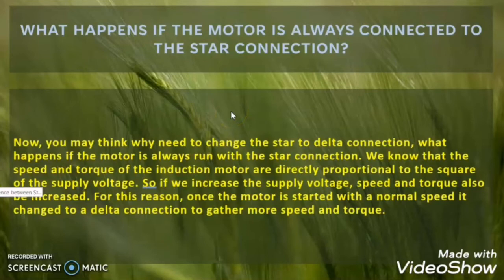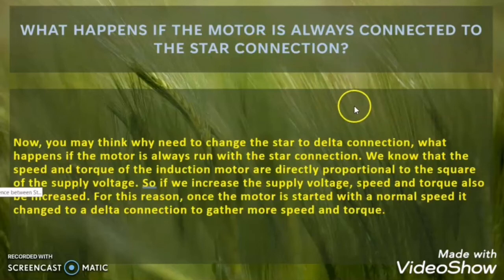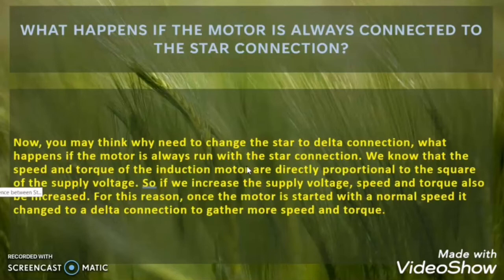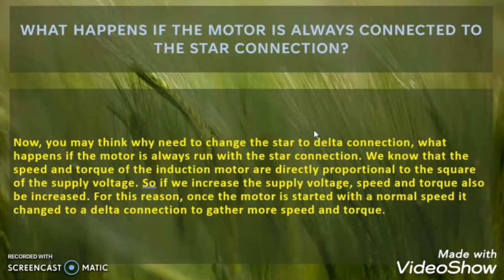No, the problem will not be solved. Suppose we connect the motor winding in star connection throughout — during starting as well as during running. Then what will happen? The motor speed and torque are proportional to voltage squared. In star configuration, the voltage across the winding is reduced. So the speed and torque of the motor will also reduce. The purpose of the motor is to do mechanical work. If we keep the motor in star throughout, we completely ignore the mechanical output. The speed and torque will be less all the time — this is not a sensible decision. We cannot compromise the mechanical output of the motor due to an electrical problem.